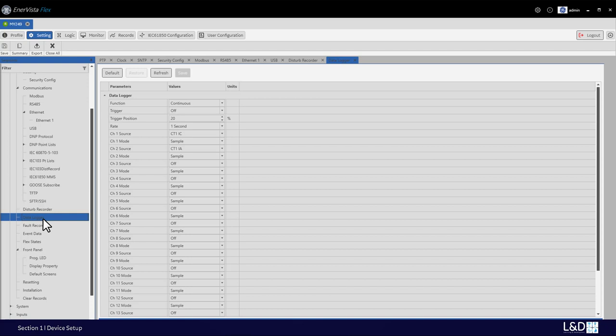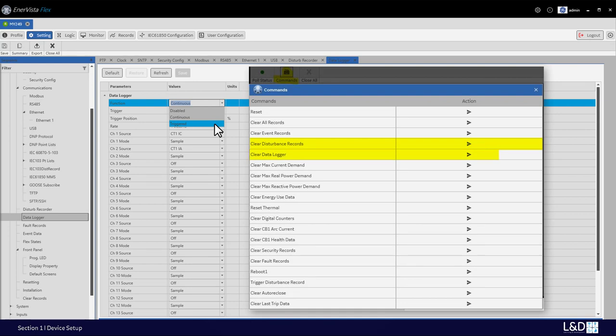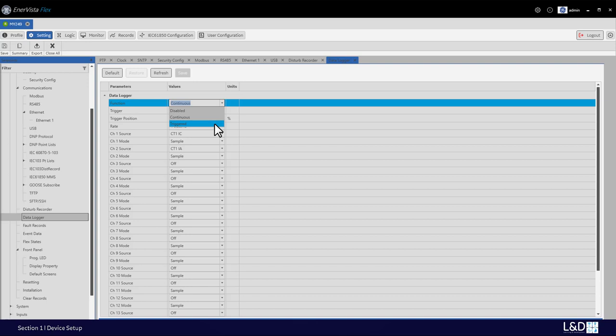For the data logger, it is used to save a much longer period of analog fluctuation. This mode can be set to continuous or triggered. In continuous mode, the logger starts recording configured analog values immediately after configuration. In triggered mode, only when the preset flex logic operand is asserted does the data logger start recording. In this mode, the data logger ignores all subsequent triggers and continues to record until the active record is full. Once the data log is full, a clear data logger command is required before you can start recording a new data logger record.